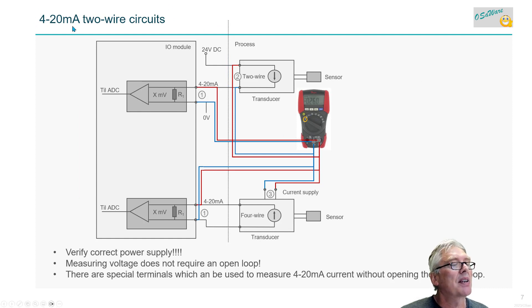Then we have this 4-20 milliamps - it's a legacy signal that's still used quite a bit. They are usually two wires. You have the sensor here, the I/O module automation device. You can measure here on the sensor itself - there should be voltage over here and there because there's a resistor sitting in here.